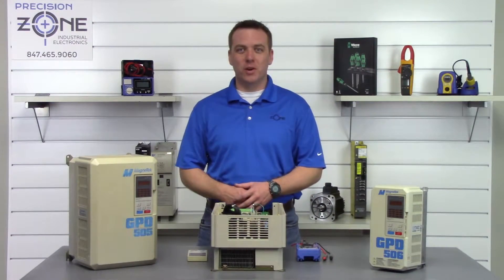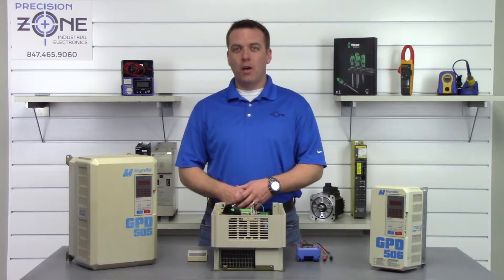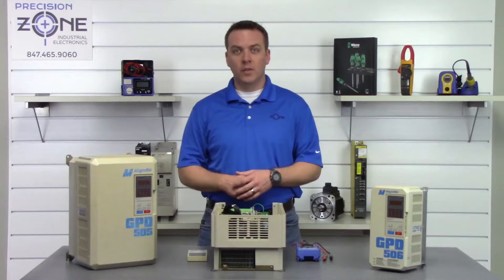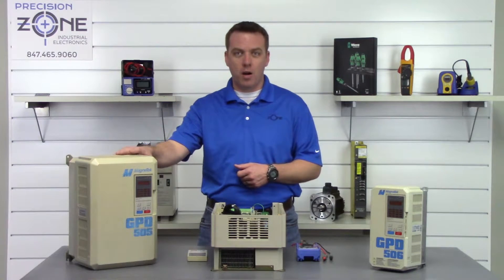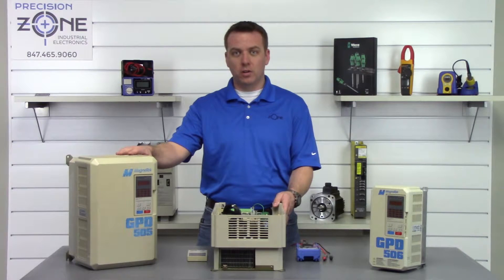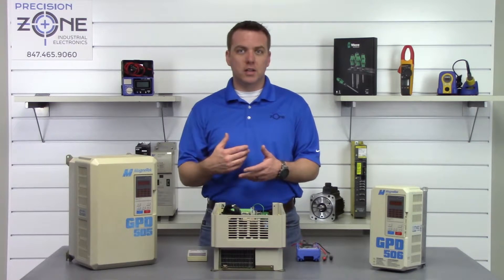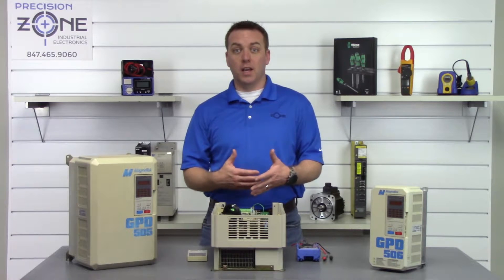Hi, I'm Rob with Precision Zone and I'm going to be showing you how to perform a quick static check on this Magnetek GPD 505 or 506 series of inverters. The first thing we're going to do is make sure that the inverter has been powered off for some time, and if you're performing this check with it installed in its application, you'll want to remove the UVW and the RST input/output cables, otherwise you're going to get a false reading.